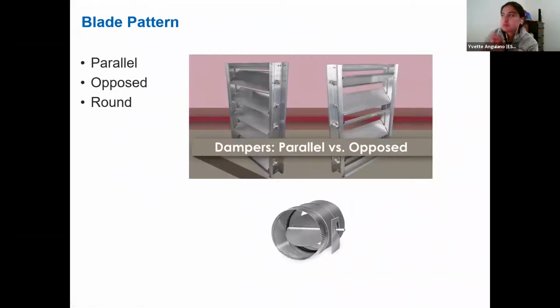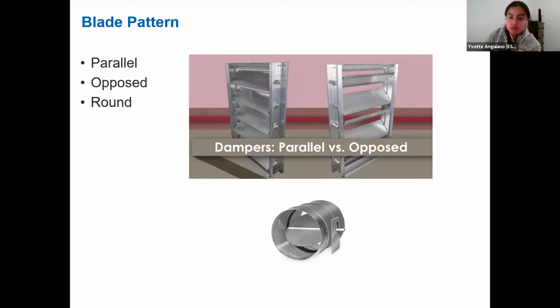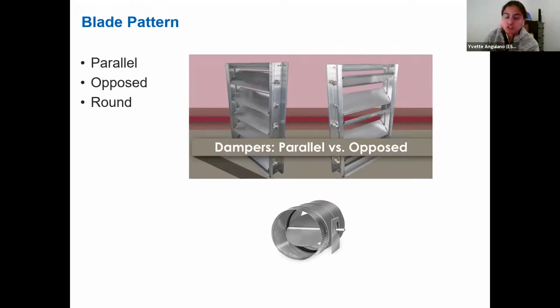So in terms of blade patterns, you've got parallel, opposed, or round. When considering a blade pattern application, you want to think about the relationship between airflow rate and the position of the blades. So for opposed blades, when you first open the blades on that damper, the relationship between the airflow rate and the position shows a nonlinear relationship. But as you start to open up that damper more, the relationship starts to become more linear and controlled. So this blade pattern would be best for a throttling application and controlling air volume, thus more appropriate for modulating applications.